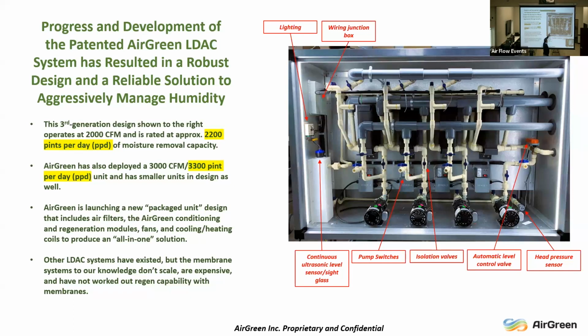We are measuring the liquid level ultrasonically, so we know where that level is, so we know what the volume is. And we have a pressure transducer here, so now we know what the liquid head is. You do a little bit of simple math, and now you know what your concentration is. So you have continuous concentration measurement, and you can see what's going on at any time. Now we've got a knob we can turn to change the concentration of the desiccant in a particular situation. And everything else is instrumented.